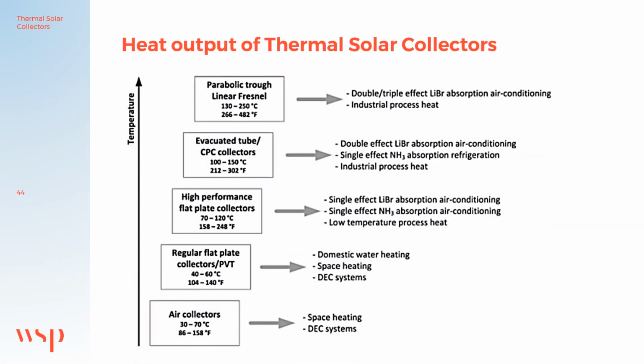This graph summarizes the heat output for each collector as well as the possible applications. Starting from the top, the parabolic trough and linear Fresnel collector can provide sufficient heat to generate chilled water using the absorption chiller, where the chilled water can be used in cooling systems. The heat can also be used for industrial process heat or space heating.